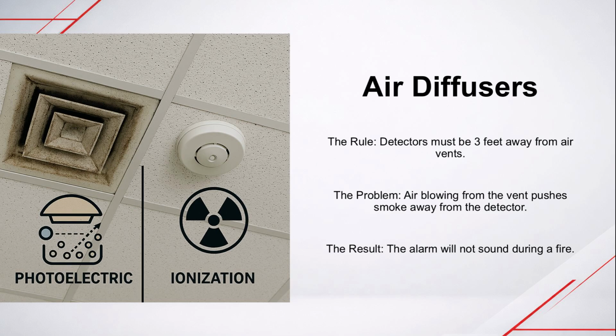You must never place a smoke detector directly next to an HVAC supply vent or air diffuser. The code usually requires a minimum distance of 3 feet. The reason is simple physics. If clean air is blowing out of a vent at high speed, it will push the smoke away from the detector. You could have a fire burning right across the room, but if the air vent is blowing on the detector, it might never go off.